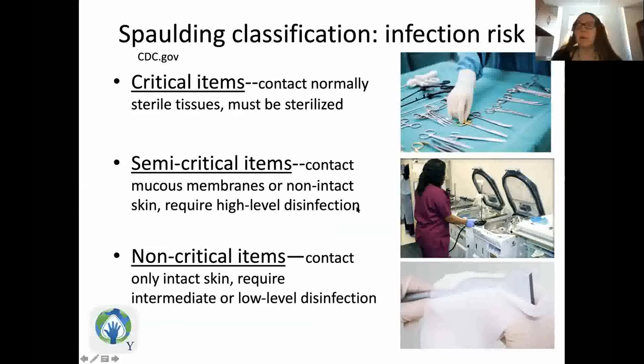So they don't need to be sterile—those areas of the body are not sterile—so they require minimum high-level disinfection. Non-critical items, things that touch the skin, like blood pressure cuffs, and you would think the handle of a laryngoscope blade, require lower, intermediate disinfection, which can be done at point of use with a chemical wipe cloth.